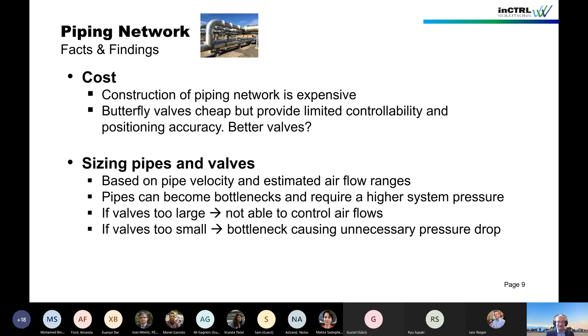Now, typically, if you're sizing pipes and valves, it's going to be based on looking at velocities in the pipe and your estimated airflow ranges. The thing that can be an issue, of course, is that these pipes potentially could be bottlenecks and may require a higher system pressure than you thought, if you didn't look at how the system would behave once the controls were in place. One common problem is that if your valves are too large, you can't have very precise control of your airflows. But if they're too small, you may have too high a pressure drop, and essentially you might be causing a bottleneck for your air supply.